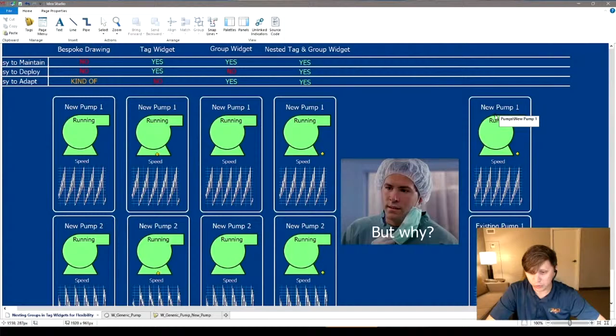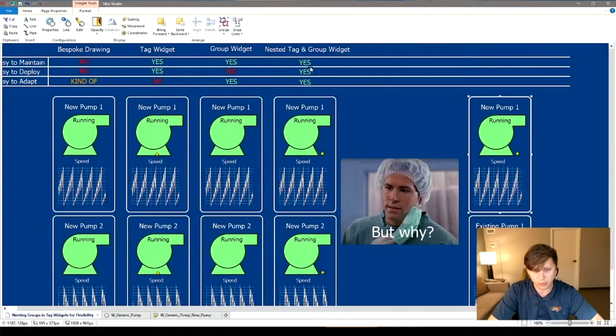So we've got a plant that we're doing that's got hundreds of pumps. We'll right-click on new pump here, and we can see, great, we've developed this widget—it works awesome. We've done this nested group and tag widget, but we've got an existing pump too. Let's take a look at its tag structure. On new pump, we've got running and speed. On existing pump, we've got P1 running and P1 speed.